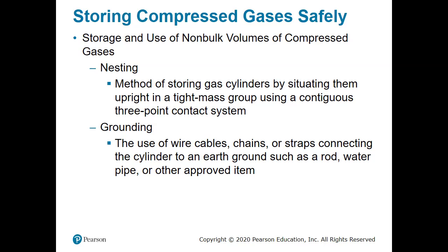Let's talk about storage. When it comes to storage, there are a couple of ways that we can store gases safely to avoid potential incidents. And the first thing that we would do in general is we would talk about how we store them. We store gas cylinders in an upright position. We don't store them laying on the ground. We don't store them in carts or dollies.